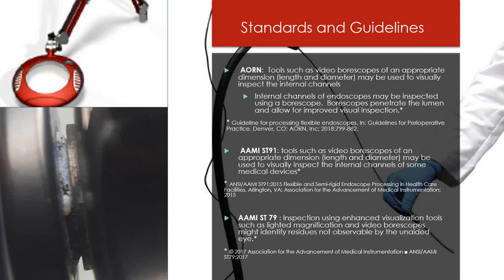AAMI ST79 states inspection using enhanced visualization tools such as lighted magnification and video borescopes might identify residues not observable by the unaided eye. The picture on the bottom left I took on a visit about a month ago; this is the control piece or control head of a flexible GI scope. I used the borescope. It doesn't necessarily have to go down the channels, it can also be used for other inspection points of the device. Here you can see there's actually epoxy coming off, and this is one of the seals that has gone bad. So this is a perfect example of using enhanced visual inspection.